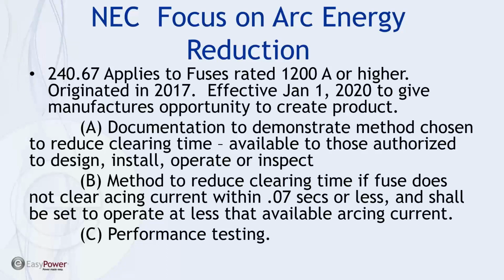And so it applies to fuses rated for 1200 amps or higher. The change in the code was actually included in the 2017 version, and it made this particular article effective post-dated as of January 1st, 2020, to give manufacturers the opportunity to create product that could be used in this application.